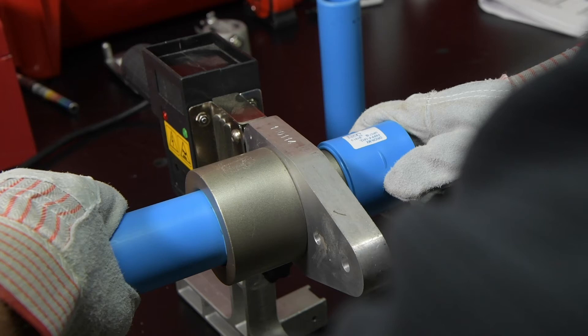Checking for this bead while the components are heating will also indicate if they're being held straight on the tool. If the bead is of a uniform diameter all the way around, the component is properly aligned on the tool. If there's a thicker and thinner area on the bead, the component is out of alignment and must be straightened.